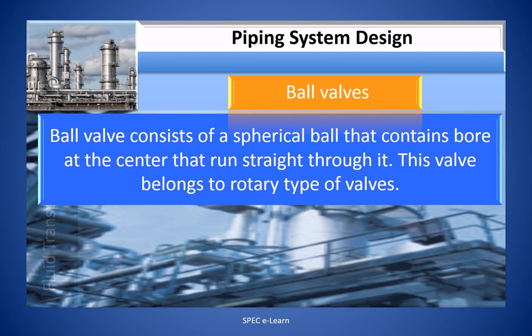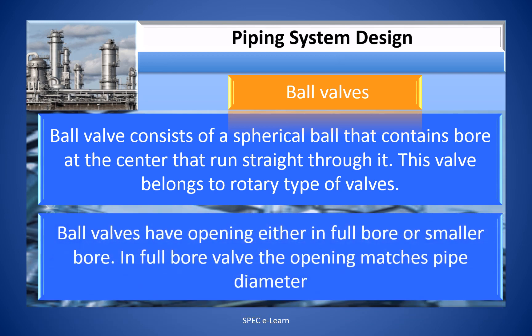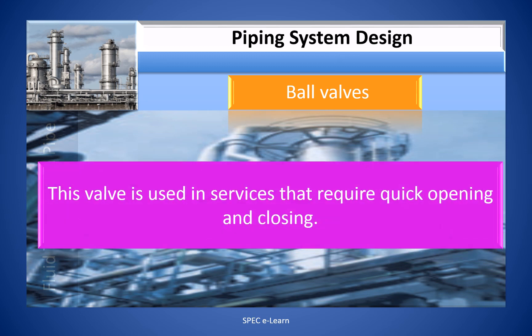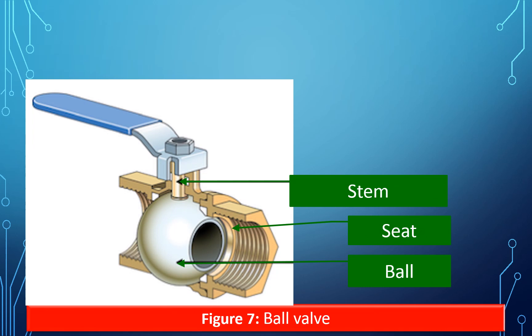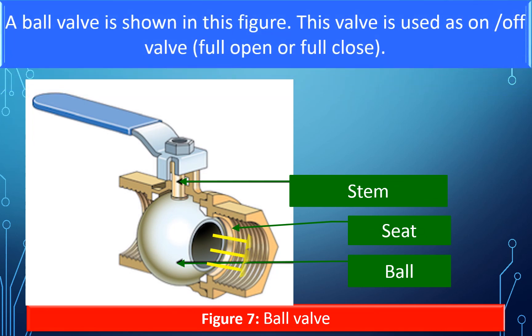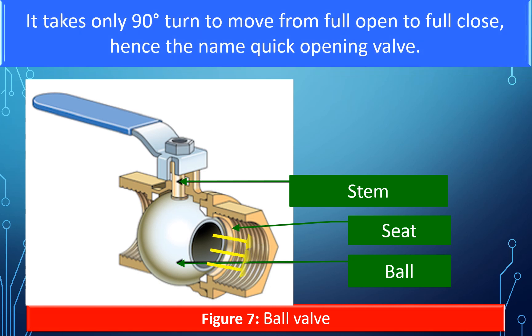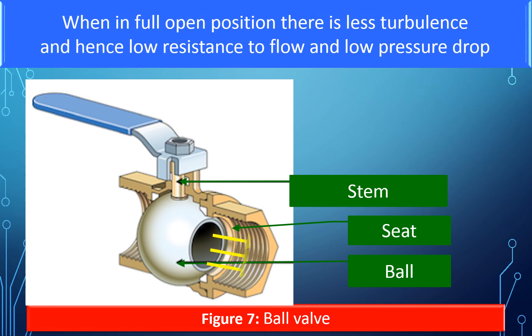The ball valve consists of a spherical ball containing a bore at the center that runs straight through it. This valve belongs to the rotary type of valves. Ball valves have openings either in full bore or smaller bore; in a full bore valve, the opening matches the pipe diameter. This valve is used in services that require quick opening or closing, as it takes only 90 degrees of turn to move from full open to full close — hence the name quick-opening valve. When in full open position, there is less turbulence, resulting in low resistance to flow and low pressure drop.